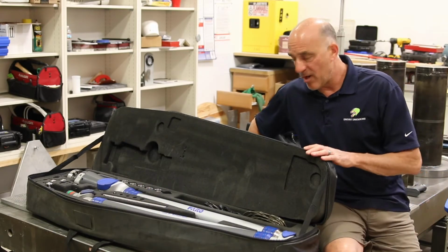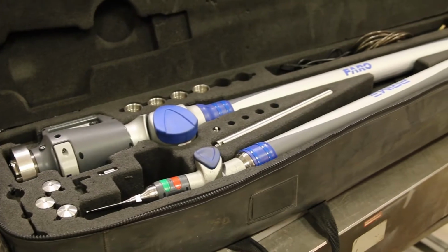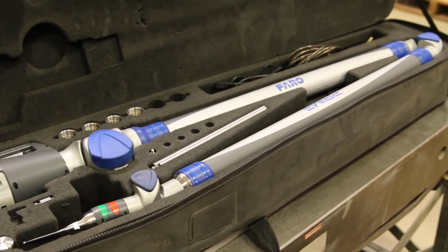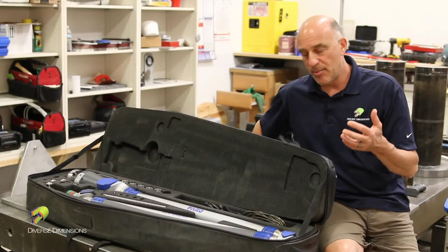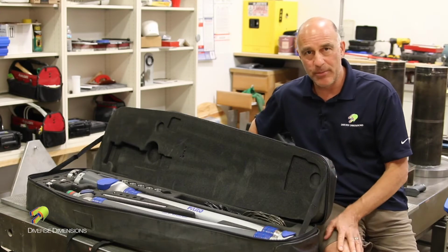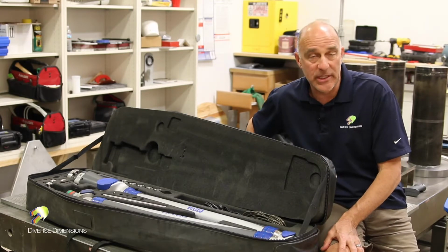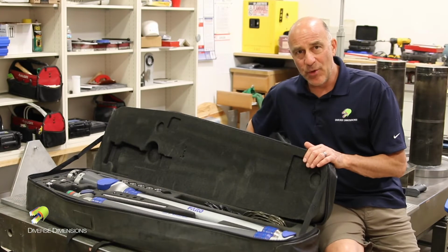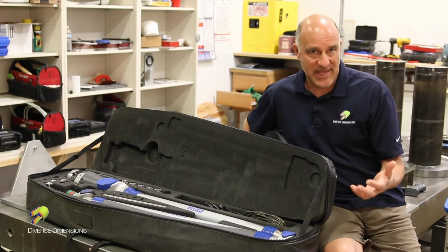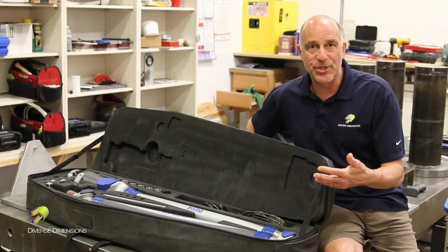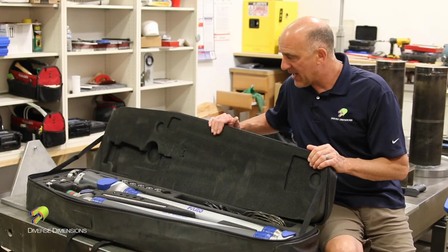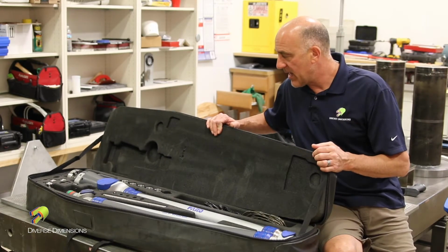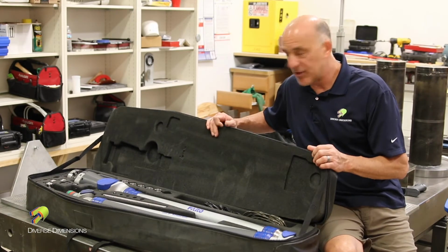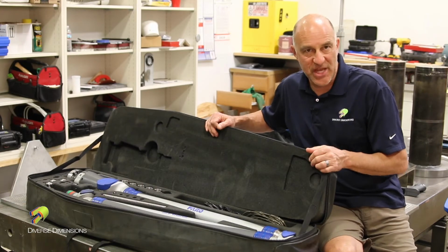I've got a prime arm here, and I wanted to show you guys how we can calibrate our prime arm. It's going to be different than our quantum arm because our prime only has 6 axes, but it's a perfect arm for shooting tooling. But the client I'm going to, we don't have a really good spot to calibrate there. So I like to do a calibration here in the lab. Then I pack it back up into our little case here, and it's fine on the transport over to our client. Then we just set up and start measuring.